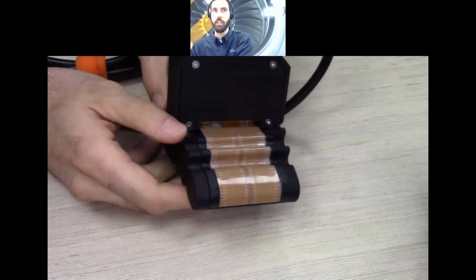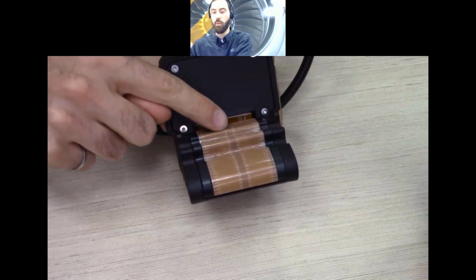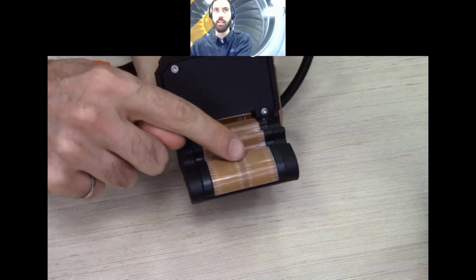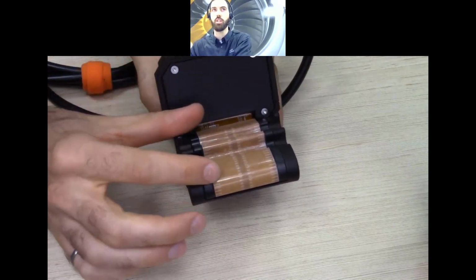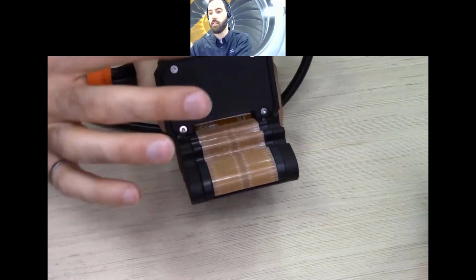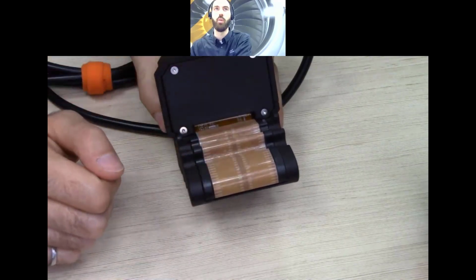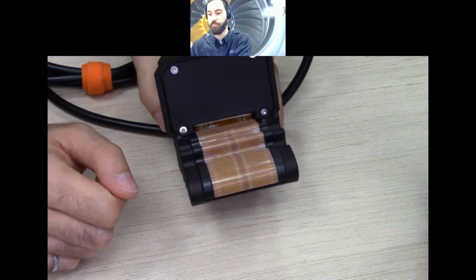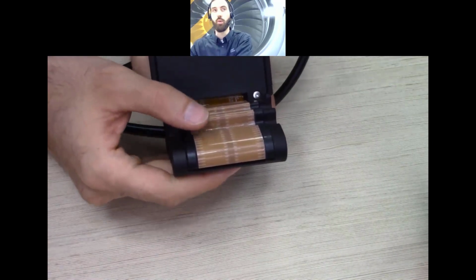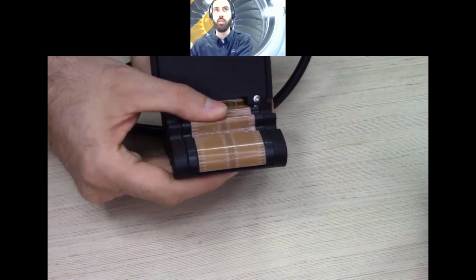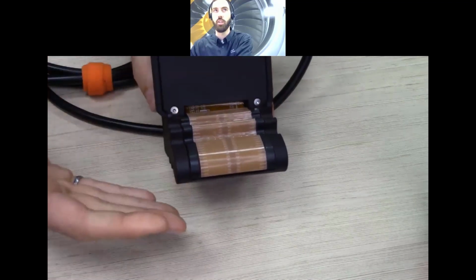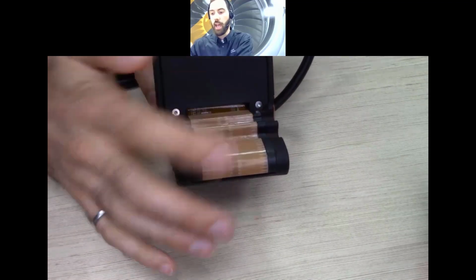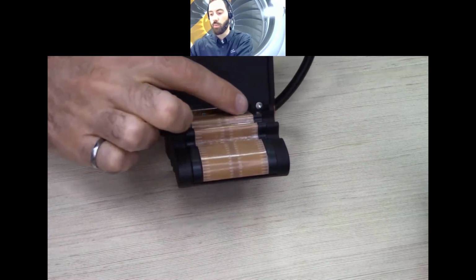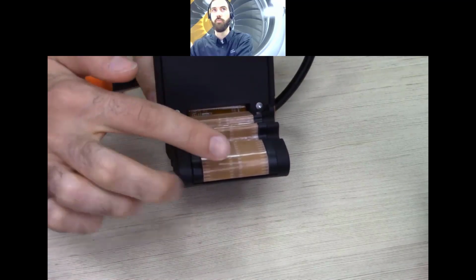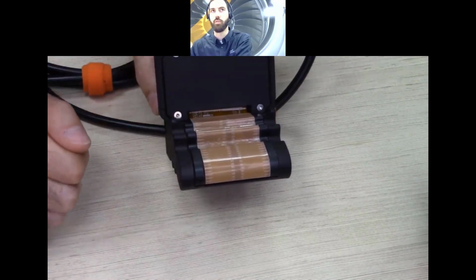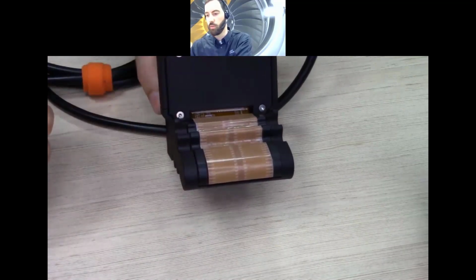So the probe we've made uses the flexible array here, you see all the coil sensors. This is essentially a custom-made version of the P-Flex, we made it longer with up to 128 channels. The probe is installed on a spring-loaded shoe to make sure it is always in good contact with the surface, and as mentioned earlier, it is also protected with a layer of PEEK to protect it from the surface. This is something we always use with those probes.